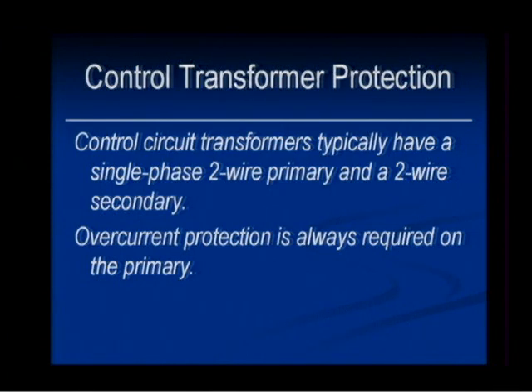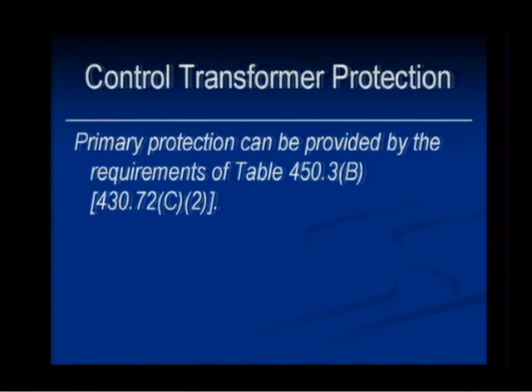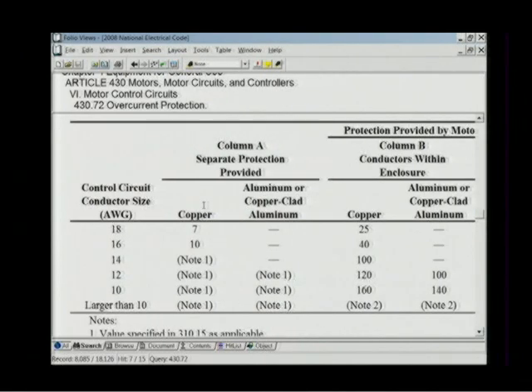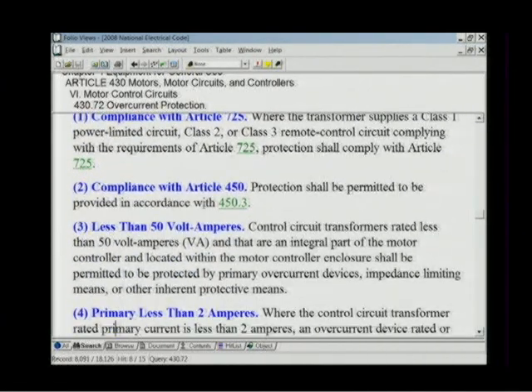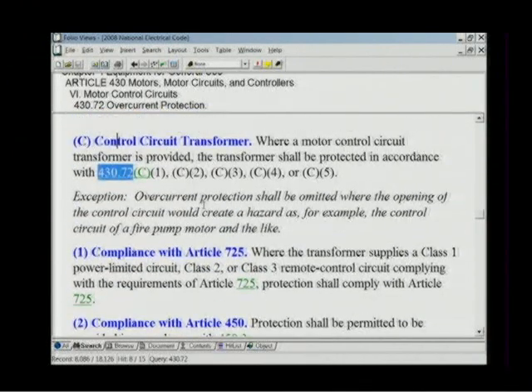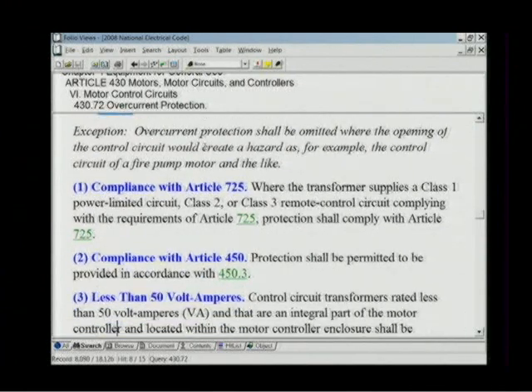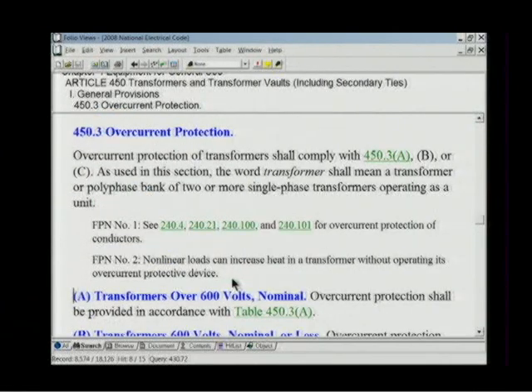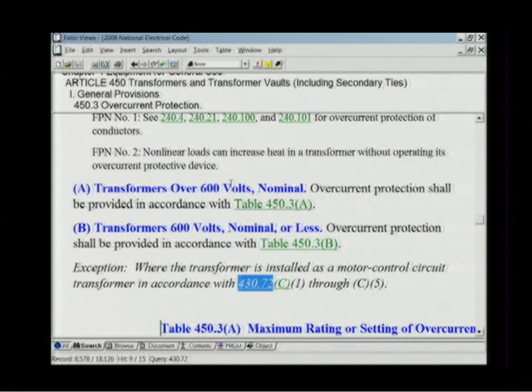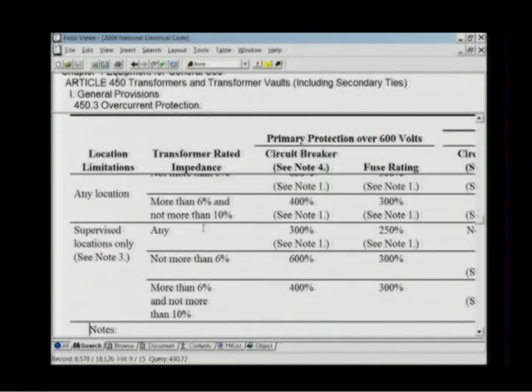Overcurrent protection is always required on the primary side of a transformer. Primary protection can be provided by the requirements of Table 450.3(B). Now that reference is from 430.72(C)(2). Let's go to the code book, 430.72(C)(2). 72(C) is control circuit transformers. Then we go to number 2, compliance with Article 450, and it references 450.3. And when we go to 450.3, (A) is over 600 volts, which we're not dealing with, and (B) is 600 volts nominal or less, which we are, then there's a table that tells you how to provide protection for transformers.